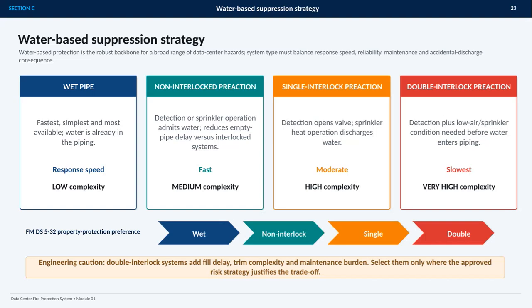This section compares 4 water-based suppression strategies for data centers. The central issue is not simply whether a system uses water, but how quickly water can reach the hazard, how complex the system is to maintain, and what the consequences would be if water were admitted accidentally.